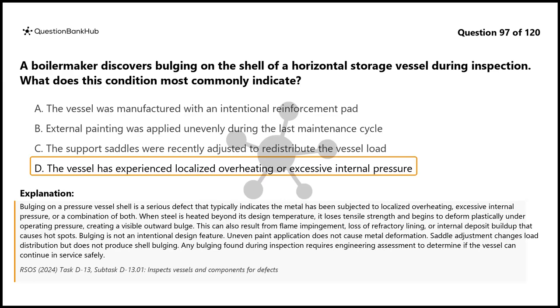Bulging is not an intentional design feature. Uneven paint application does not cause metal deformation. Saddle adjustment changes load distribution but does not produce shell bulging. Any bulging found during inspection requires engineering assessment to determine if the vessel can continue in service safely.